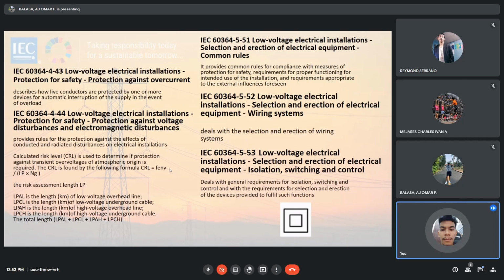Overload detection shall be provided for the neutral conductor in a multi-phase circuit where the harmonic content of the line currents is such that the current in the neutral conductor is expected to exceed the current-carrying capacity of that conductor. Where the neutral conductor is distributed, it is necessary to provide overcurrent detection for the neutral conductor of every circuit. The overcurrent detection shall cause the disconnection of all the live conductors of the corresponding circuit, including the neutral conductor. This measure is not necessary if the particular neutral conductor is effectively protected against overcurrent by a protective device placed on the supply side.